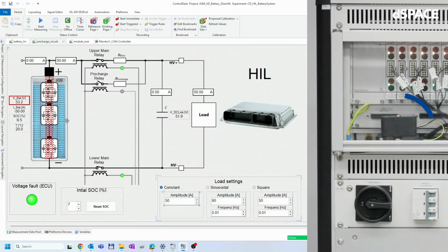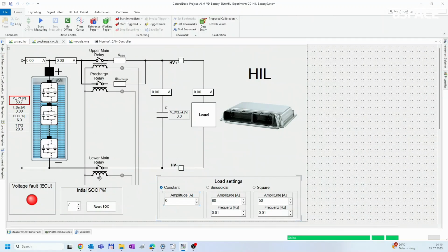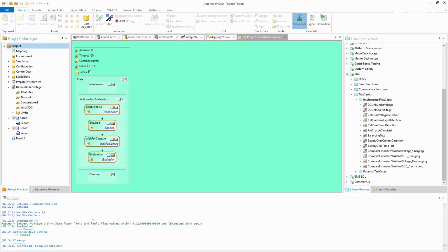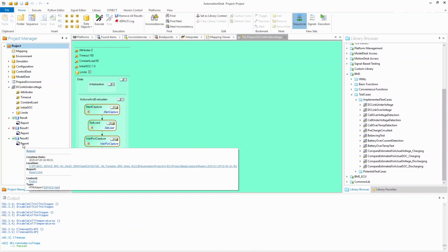Yeah, not surprisingly, again the ECU gives a warning indication, as I saw in the very first manual run. And once we approach the 53 volts, the voltage fault will be raised again. Okay, this happened as expected. Again, the upper and lower main relay were opened, and the test case was successful. Also, AutomationDesk is indicating this here and is generating another report, as you can see here.